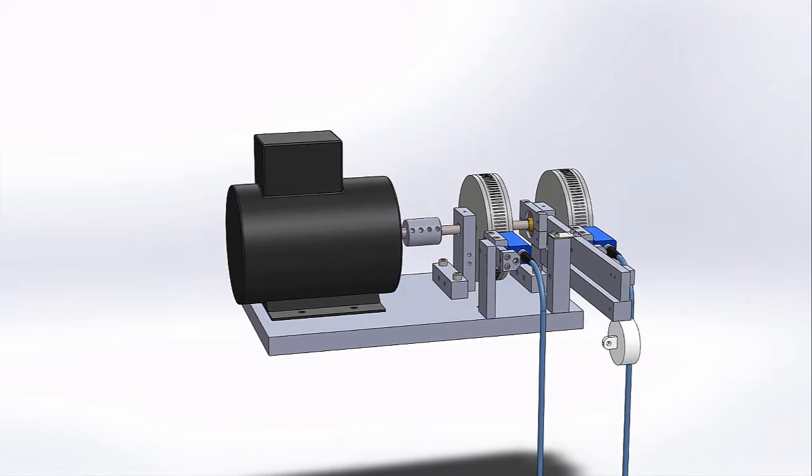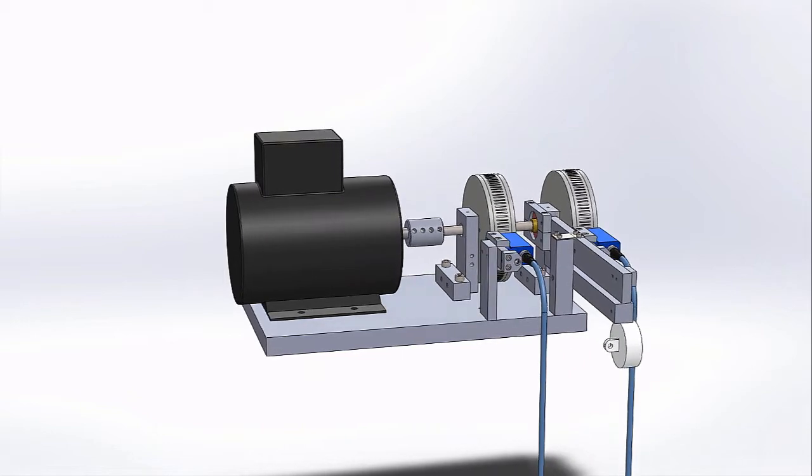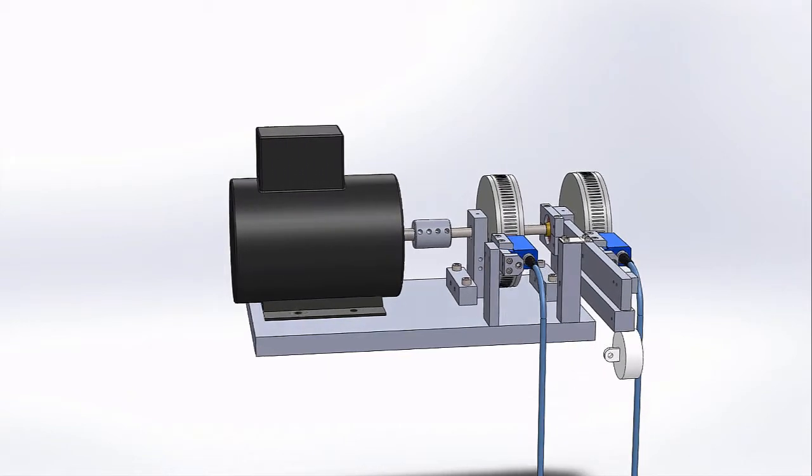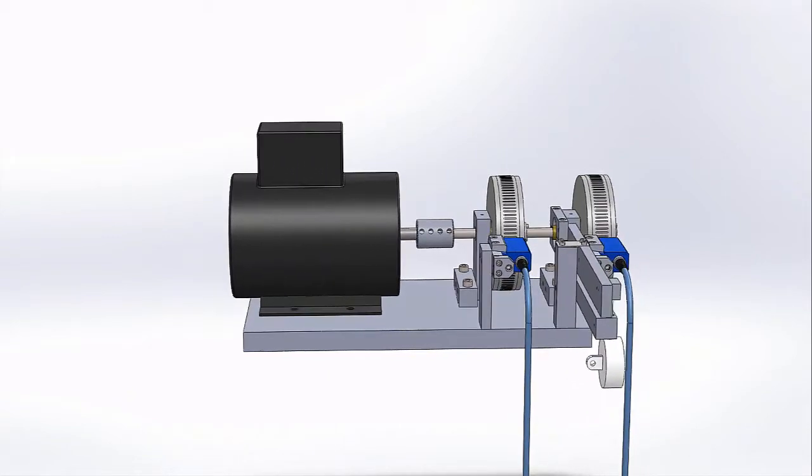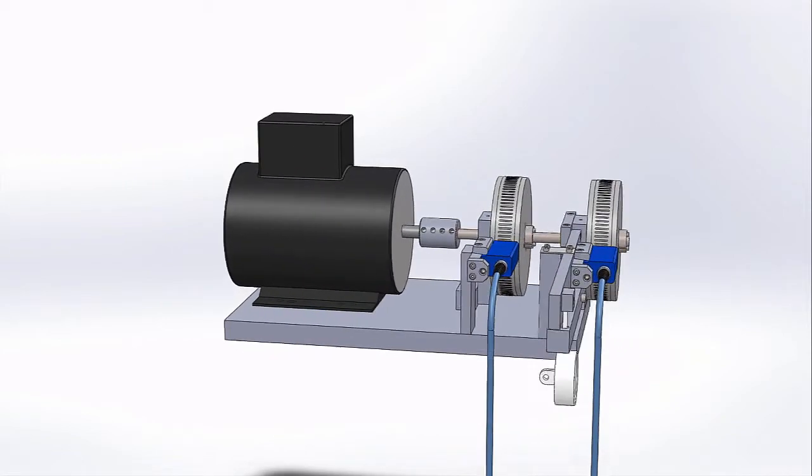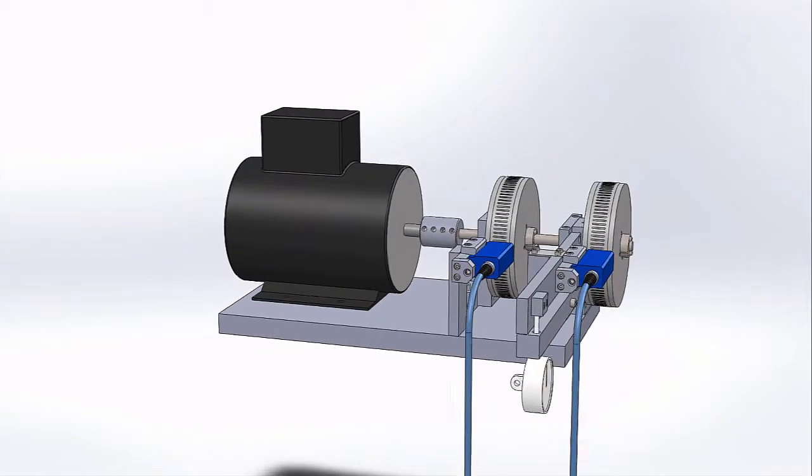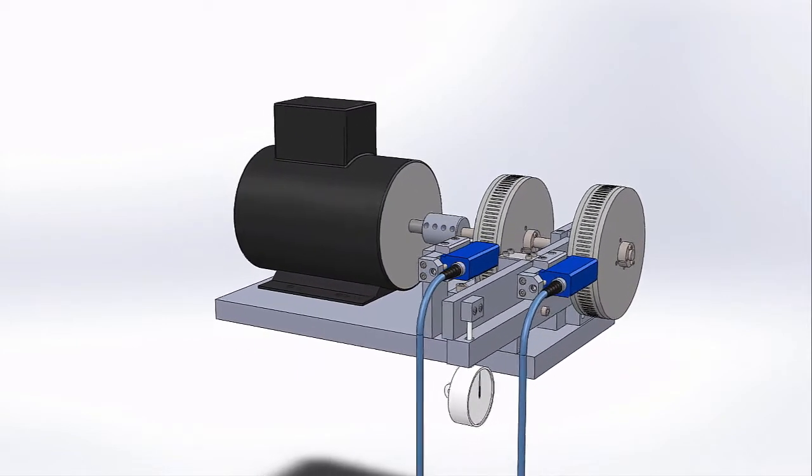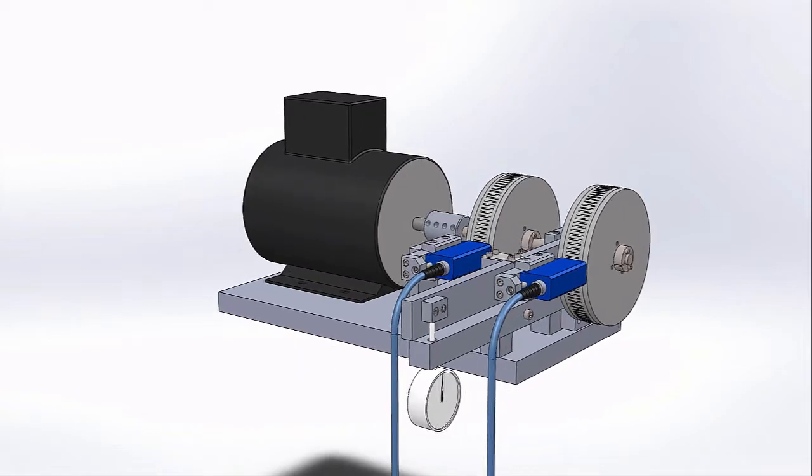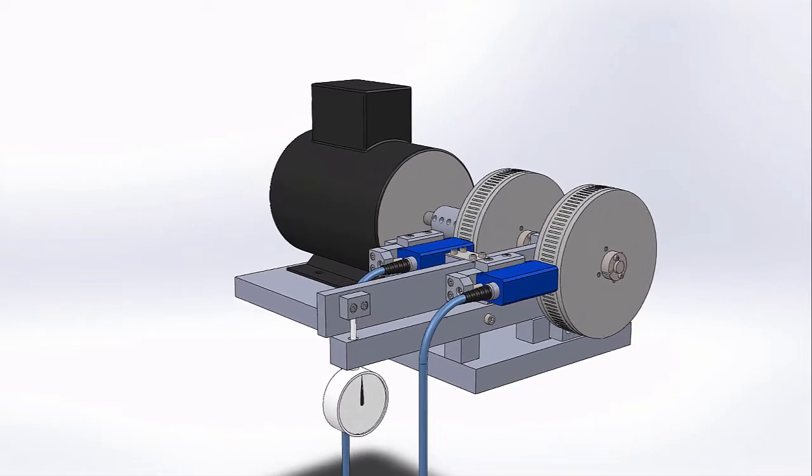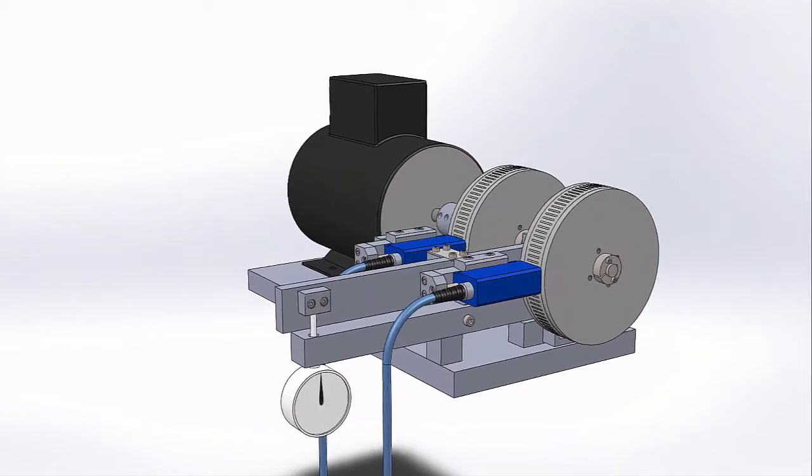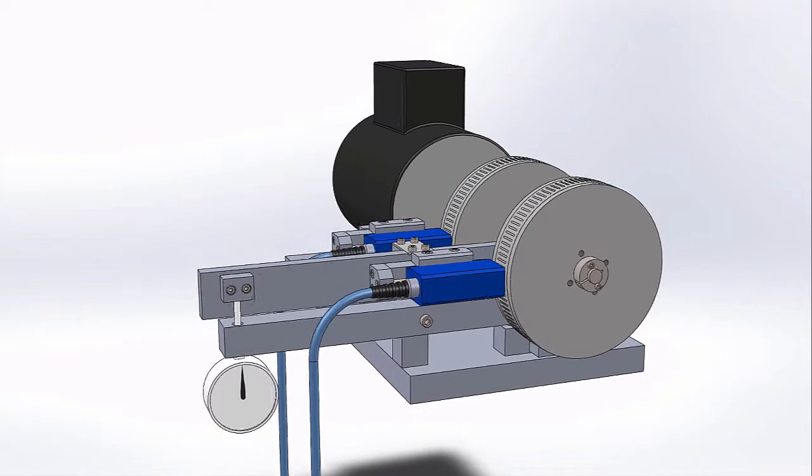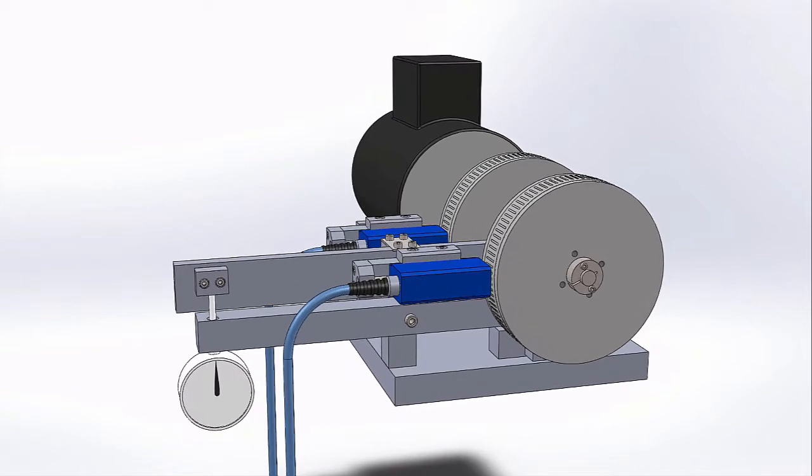The field installation requires attaching the sensors to rigid and stationary bases at two different locations along the shaft. The relative angular twist is measured between these two locations continuously with high precision, since it is really difficult to twist a rotating shaft with a predetermined angle.